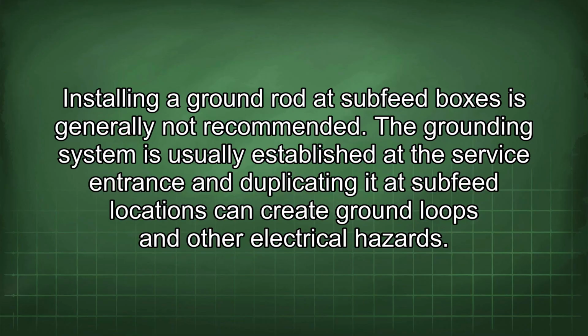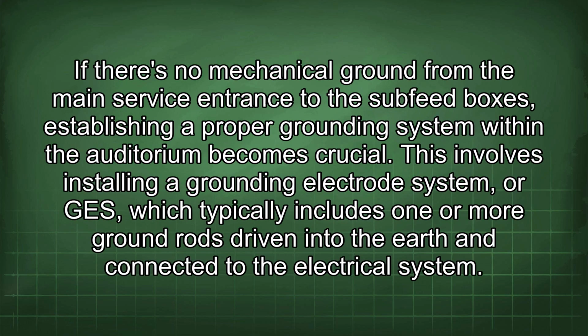Installing a ground rod at sub-feed boxes is generally not recommended. The grounding system is usually established at the service entrance, and duplicating it at sub-feed locations can create ground loops and other electrical hazards. If there's no mechanical ground from the main service entrance to the sub-feed boxes, establishing a proper grounding system within the auditorium becomes crucial.